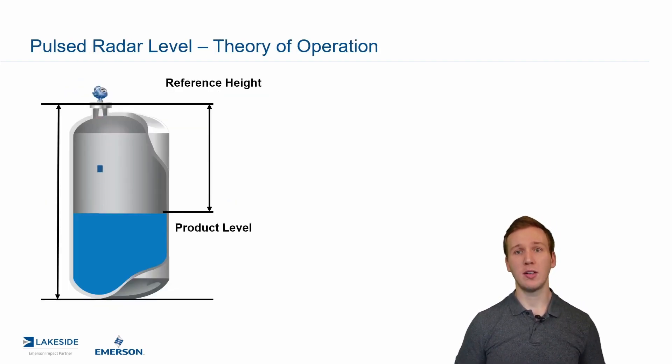If we look at pulsed radar, this is what many of us might be familiar with. It is a time of flight measurement. As you can see pictured beside me here, we have our non-contacting radar mounted at some sort of reference height, and then the product is a certain distance away. As you can see, it is shoot, waiting, and then receiving a reflection back off of that product's surface.